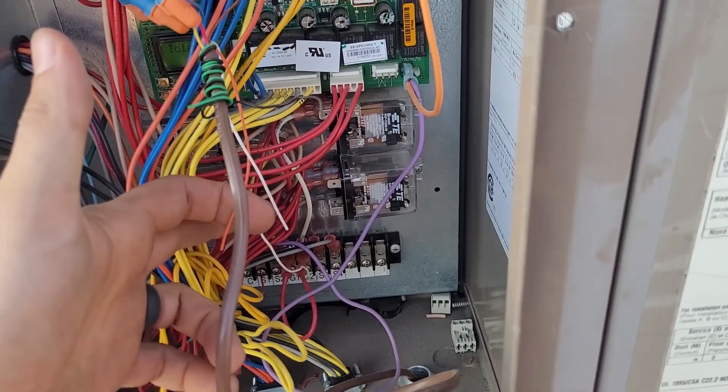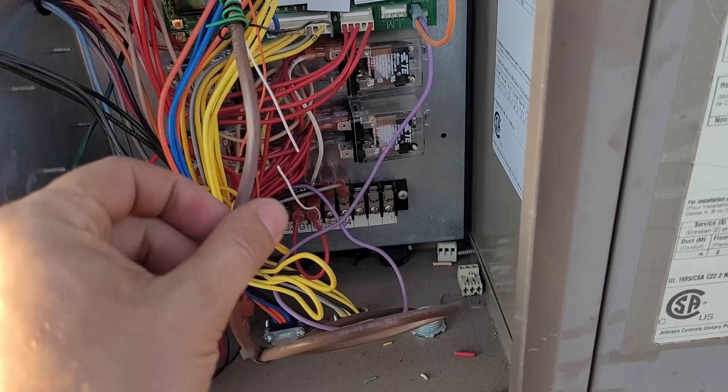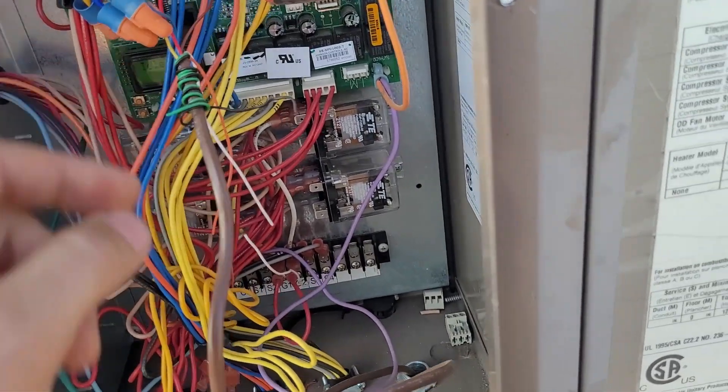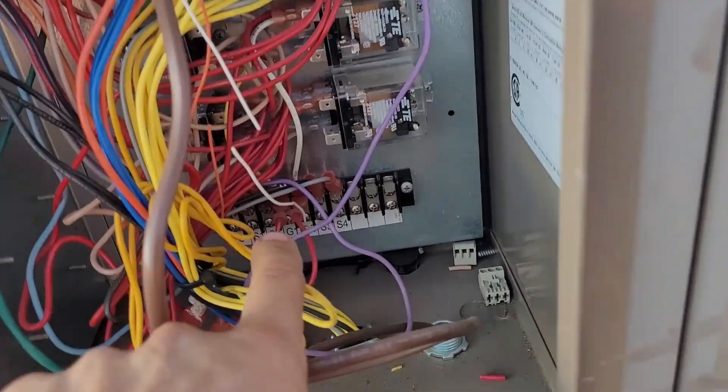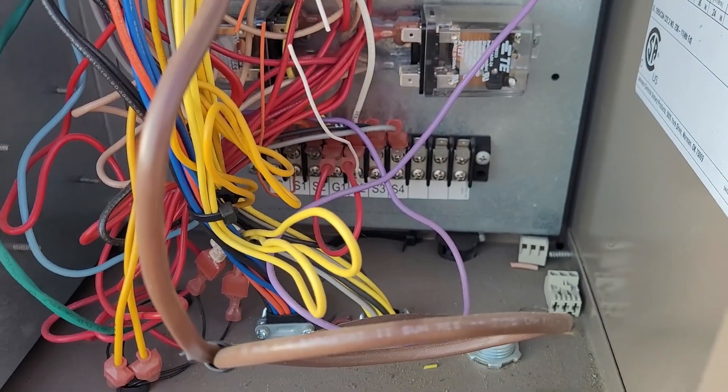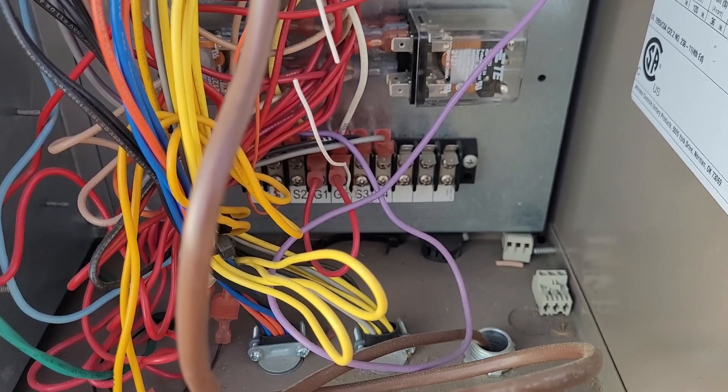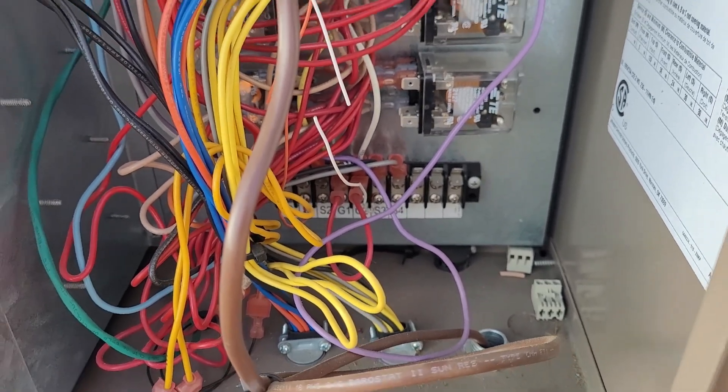The orange was stage one, so this comes up from the controller, and it goes to S1 down there. The other one goes to S3, so Y2 goes to S3.